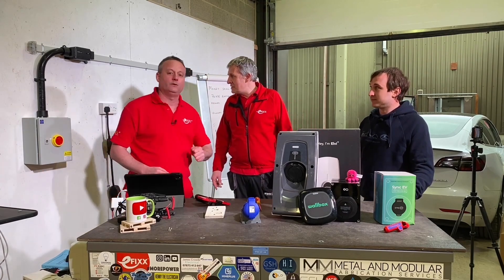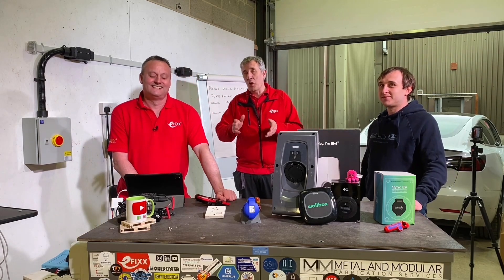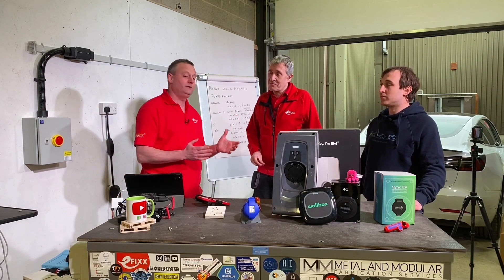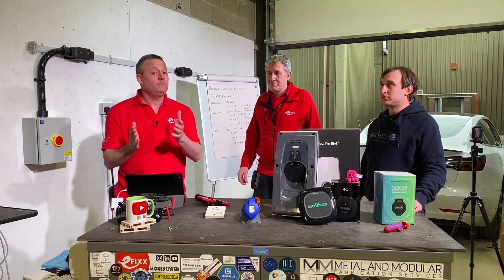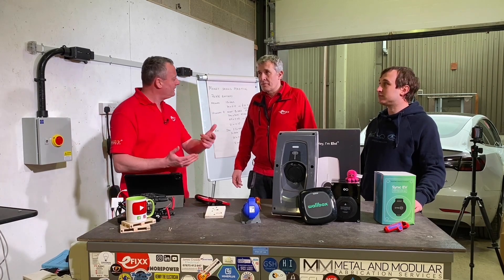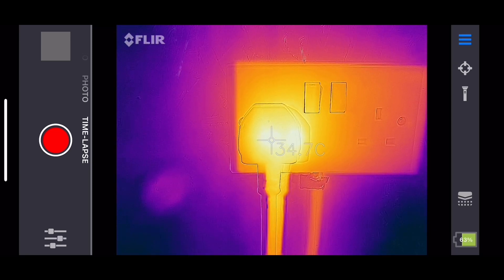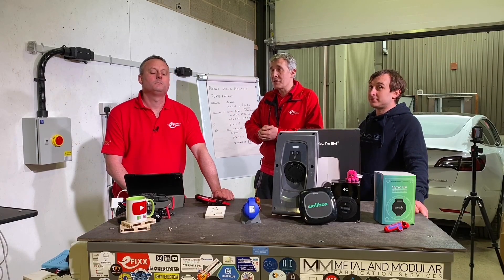On a 13-amp socket you're going to be plugging in for an incredibly long amount of time, and 13-amp sockets weren't originally designed for that. They're actually limited to 10 amps for a continuous period of time, so a circuit in your home that possibly wasn't designed to take 10 amps for 20-odd hours is going to be under stress charging your car. We've done some measuring with our thermal camera - this is a brand new socket, but after just an hour's use the socket outlet itself has heated up in temperature quite considerably.